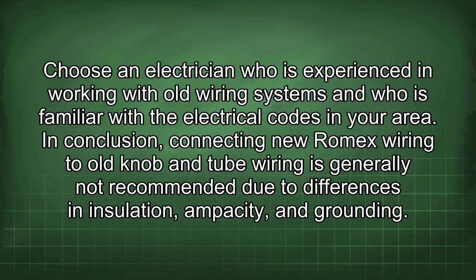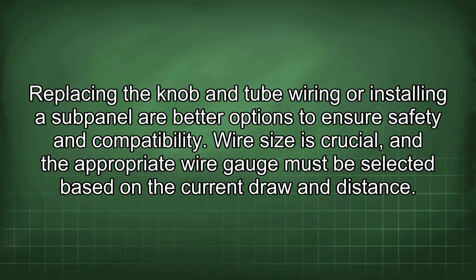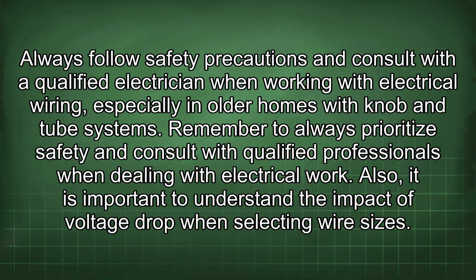In conclusion, connecting new Romex wiring to old knob and tube wiring is generally not recommended due to differences in insulation, ampacity, and grounding. Replacing the knob and tube wiring or installing a subpanel are better options to ensure safety and compatibility. Wire size is crucial and the appropriate wire gauge must be selected based on the current draw and distance. Always follow safety precautions and consult with a qualified electrician when working with electrical wiring, especially in older homes with knob and tube systems. Remember to always prioritize safety and consult with qualified professionals when dealing with electrical work.